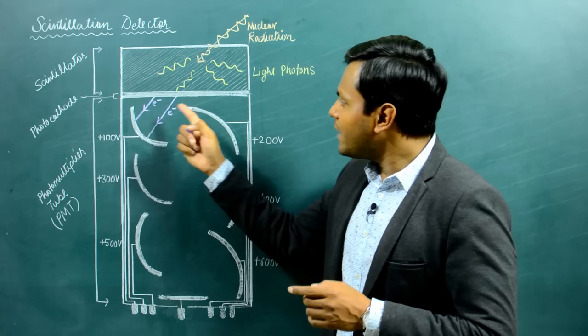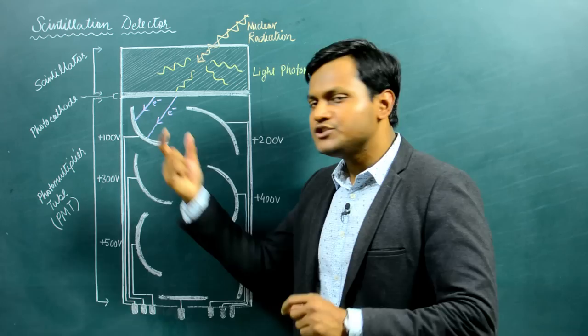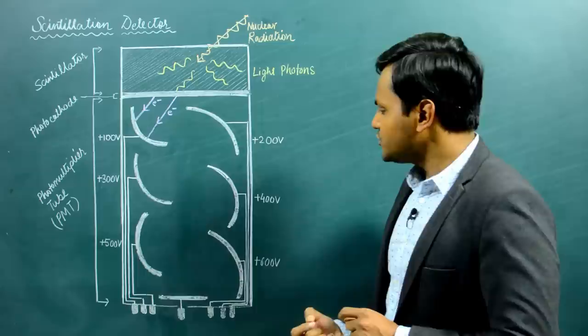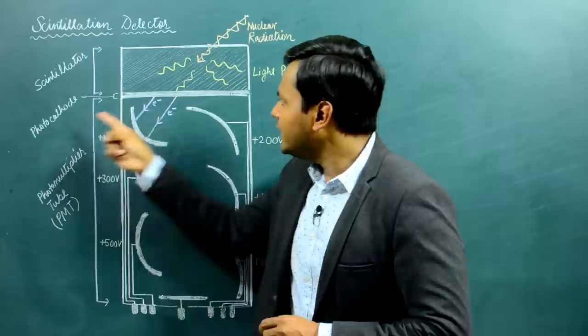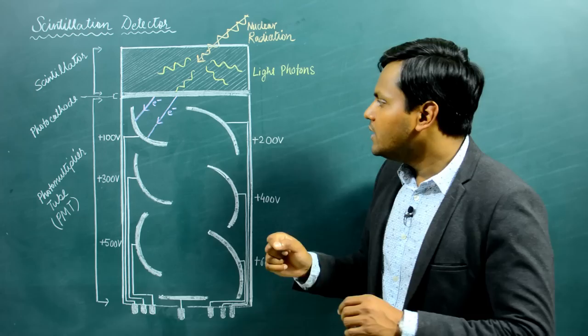These primary photo electrons then enter the photomultiplier tube. The purpose of the photomultiplier tube is to increase the initial photo electrons to a very high value so that it can lead to a significant current pulse in the connected electronics. There is a particular geometrical construction inside the photomultiplier tube. When the light photons hit the photo cathode and emit photo electrons, these photo electrons are directed towards an electrode at +100 volts. These curved electrode surfaces are known as dynodes.